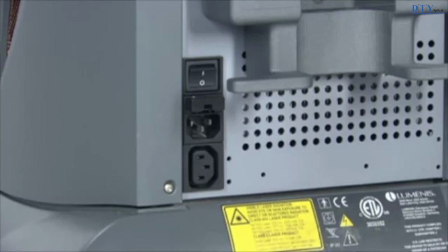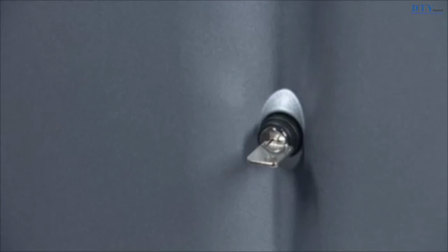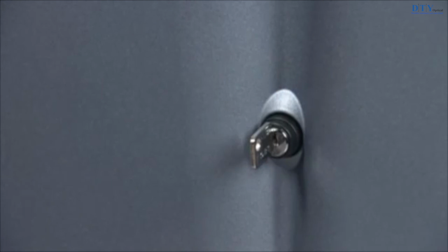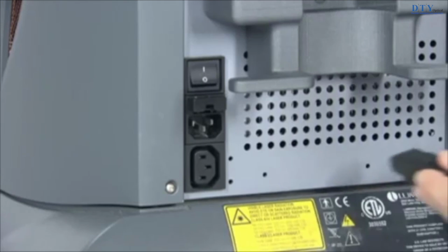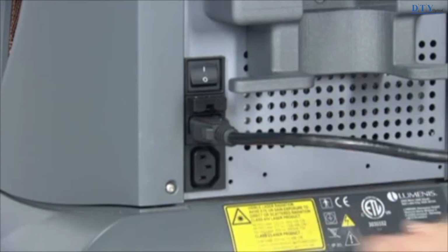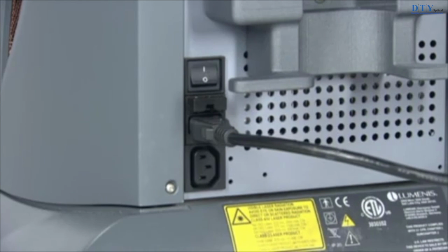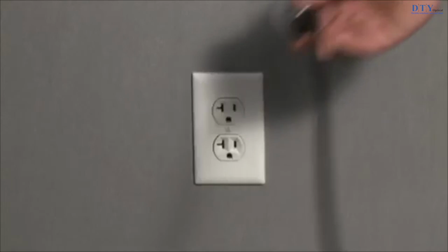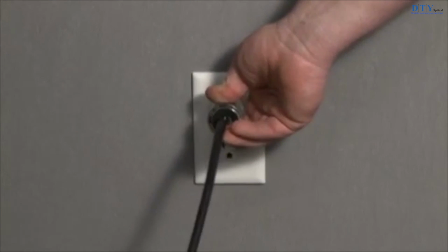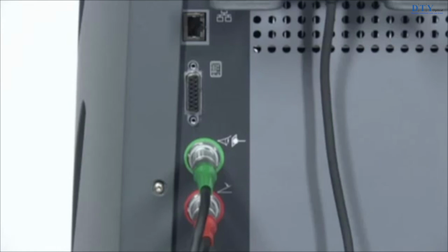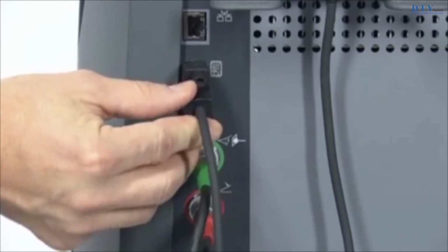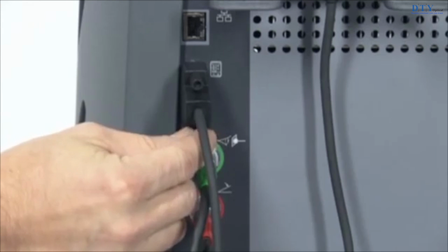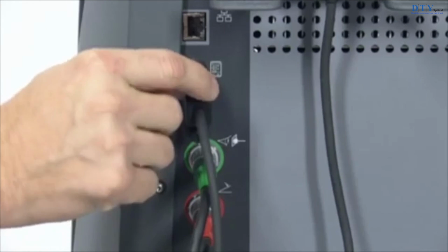The main power cable will vary in appearance according to the electrical requirements of the country in which the laser will operate. First, ensure that the key switch is in the off position. Next, insert the matching end of the main power cable into the main power receptacle on the rear of the laser's console. Finally, insert the main power plug into the wall socket. You may connect the remote control at any time by inserting the remote control plug into the remote control receptacle on the rear of the laser console. Secure it with the thumb screws.